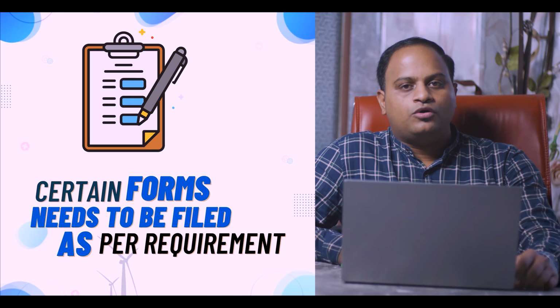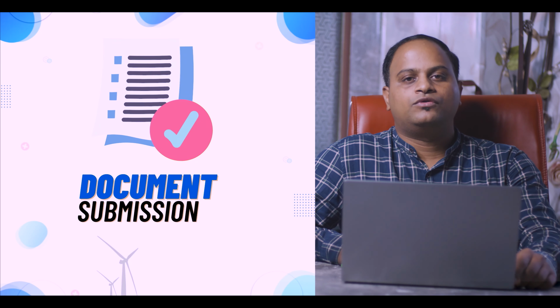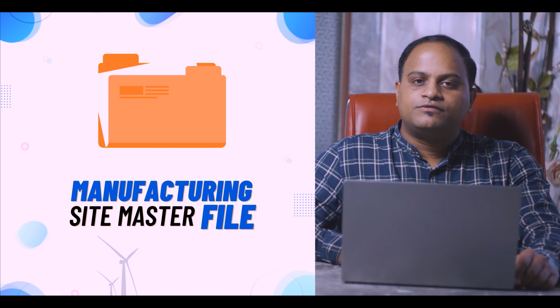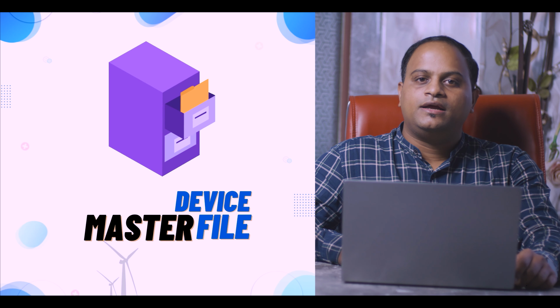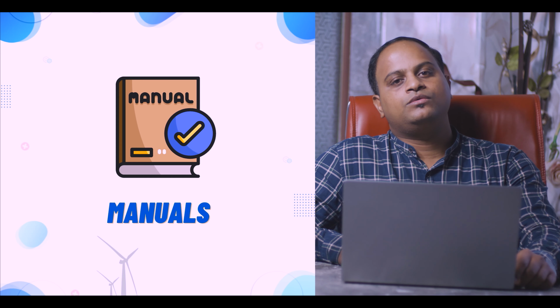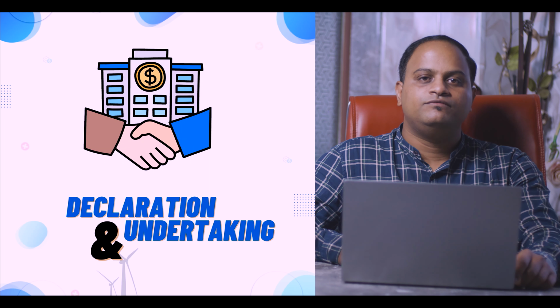First, the relevant forms available on the portal are filled as per your requirement. After that, some necessary documents are required for the approval process, like the site master file, device master file and their manuals, and declarations and undertakings, which are a necessary requirement for filing the CDSCO documentation.